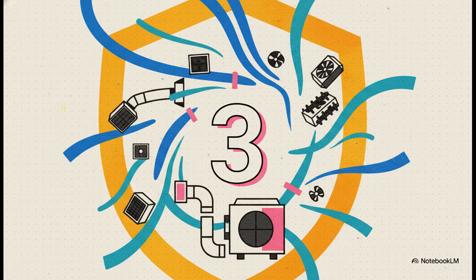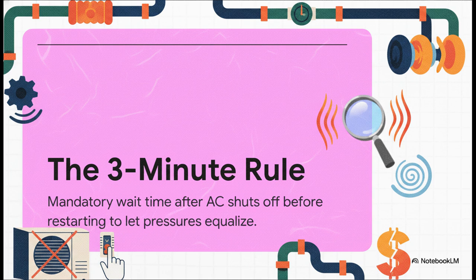Now here's another incredibly simple yet vital number for you: 3. This is a number that could literally save your system's most expensive component. This is the 3-minute rule. It's the mandatory wait time you have to give your air conditioner after it shuts off before restarting it. Why? Well, it allows the highly pressurized refrigerant to equalize safely within the system. Starting it up too soon, like when you impatiently flick the thermostat down on a sweltering day, forces the compressor to work against completely unbalanced high and low pressures. That one simple, everyday mistake can cause an instant, insanely expensive compressor failure. Just remember, always wait 3 minutes.